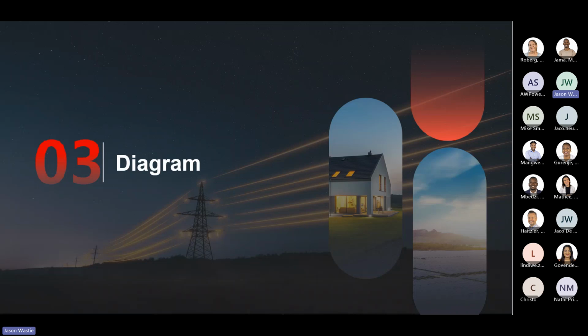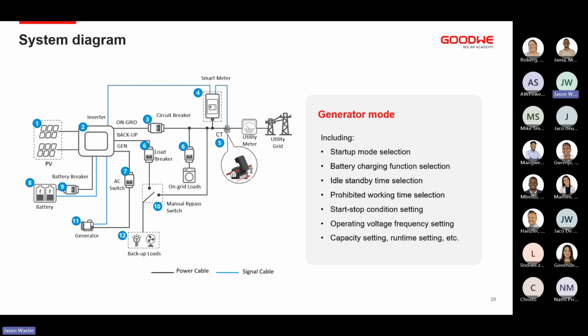Then we'll look at some of the diagrams for the ES Unique and then some of the modes as well. This is just a standard system setup with the generator connected to the third AC output. We have got our PV panels connected, the smart meter, which is only needed if the DB is more than 10 meters, but up to 25 meters away. The grid is connected along with critical on-grid loads. And then we have got our battery backup connected as well as AC backup loads with the manual bypass switch.